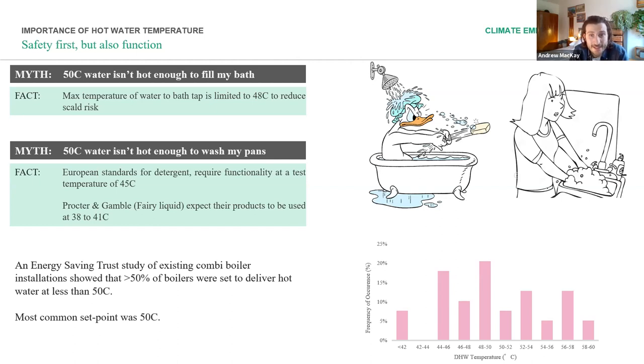And actually, when we compare that to what people are doing when they've got free choice out in the field, Energy Saving Trust did a study of combi boilers across the UK and looked at what temperature they were set at. And actually the majority of them, more than 50% of the boilers, were set to deliver hot water at less than 50 degrees. So as a country, we were already more or less happy with it.